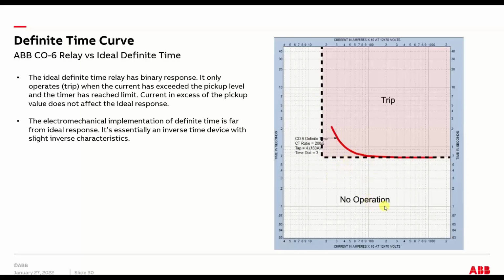And so definite time is used for things like that 51 time delay, and a lot of functions that are not involved with current, like overvoltage. It's basically hit a pickup value, wait a certain amount of time, a preset time, and then trip or not trip.